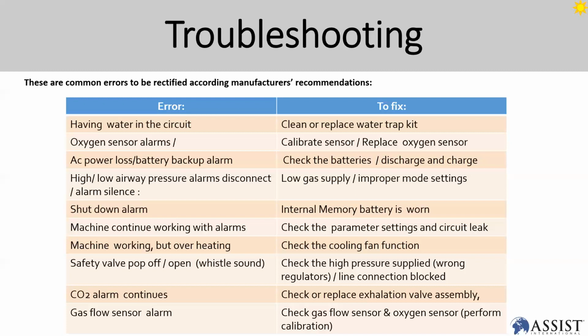An internal shutdown alarm can be caused by the internal memory battery being low. Eventually your screen becomes blank, all this. If it continues working with an alarm, check your parameter settings or circuit leakage. Try to do self-calibration, see if there is any fail, and try to troubleshoot that particular point, narrowing down your problem. Maybe it is caused by your flow sensor or pressure sensor, or your breathing circuit is broken or something like that.